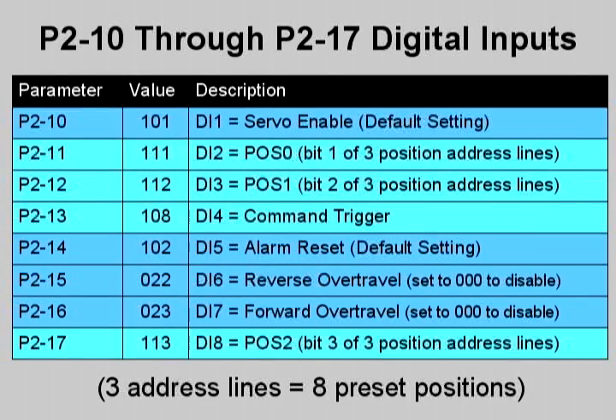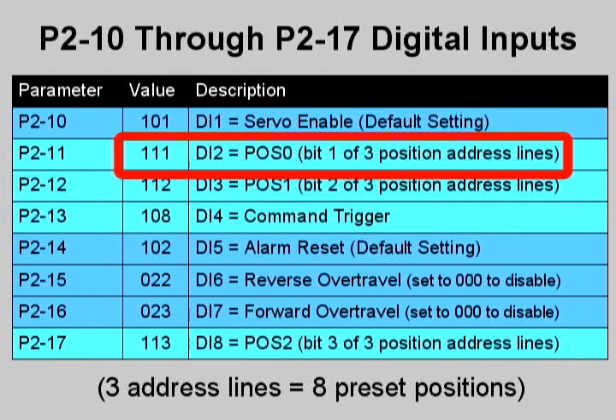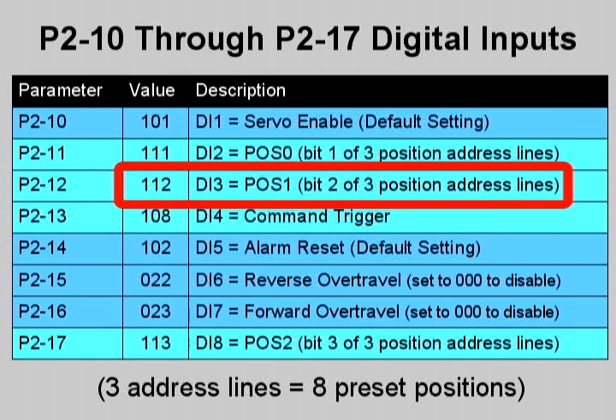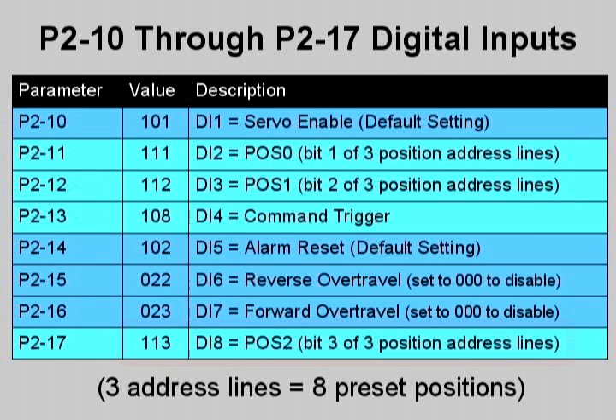Configuring the position selection inputs. The drive can be configured to select the internal position set points by using three digital inputs, POS0, POS1, and POS2. Any of the digital inputs can be set as POS0, that's code 11, POS1, that's code 12, or POS2, code 13. By configuring all three inputs, all of the eight internal presets can be selected via external signals.